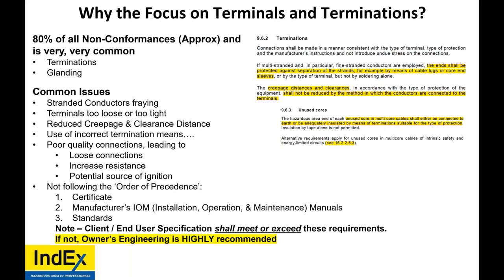When the glander has had problems and there are things that need to be punch listed, usually it's the same for terminations. So common issues: stranded conductors, fraying, terminals too loose or too tight, reduced creepage and clearance distances, use of incorrect termination means, and poor quality connections, which lead to loose connections, increased resistance, and a potential source of ignition. Increased heat and temperature rise are not good for hazardous areas. Not following the order of precedence.